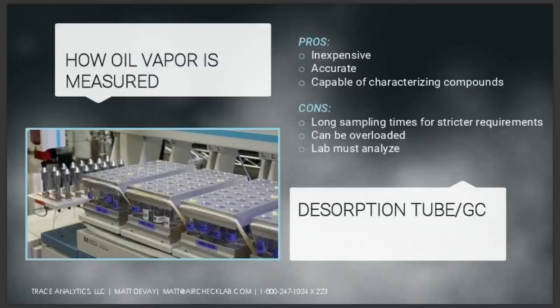The cool thing about this is that not only are you getting pretty accurate representations of what your oil vapor actually is, but you can also get it characterized and know exactly what's contaminating your system. So this tends to be a fairly robust and reasonable compromise to having inline instrumentation. One other thing you need to be aware about, though, is if you've got high levels of oil vapors in your system, very likely that you can overload the tube, and you're going to get a result back that you can't really use in the face of an audit.